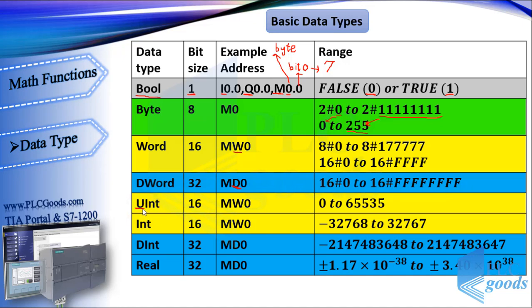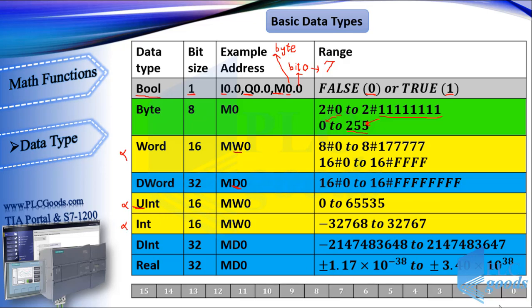Pay attention to unsigned integer and integer format. Like the word format, these need 16 bits, but the way they are stored is different. Unsigned integer uses all 16 bits to store a positive number from 0 to 65535. The integer format uses the last bit for sign, so it only uses 15 bits to store numbers — 0 means positive and 1 means negative. It supports numbers from -32768 to 32767. Double integer with 32 bits supports a larger range.